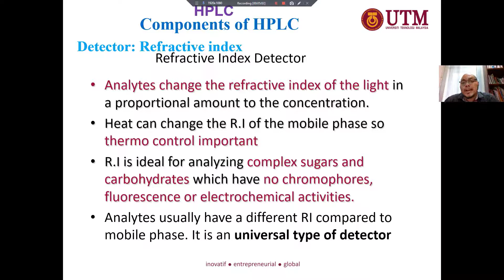Here are the plus and minus points for the refractive index detector. The RI detector measures a bulk property, so it's not necessary for the compound to have a chromophore. It is nearly universal, so you can detect nearly everything as long as the RI differs from the mobile phase. It gives a comparable response for different analytes and detects species with no chromophore. This is the advantage of the RI, so you need to understand this.